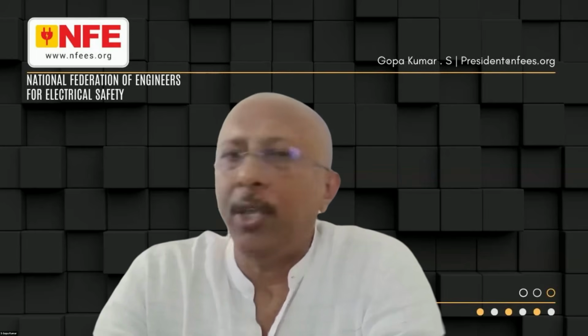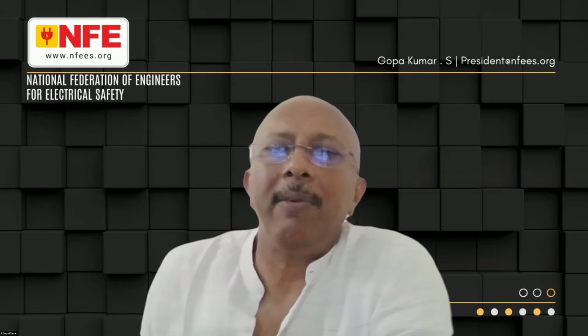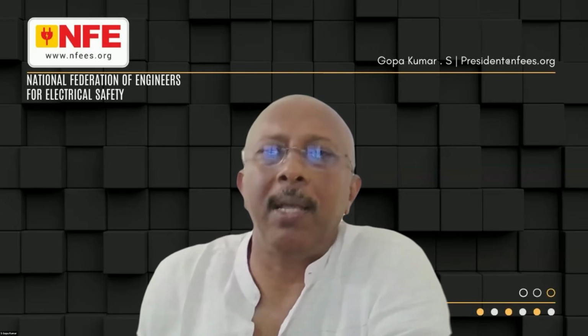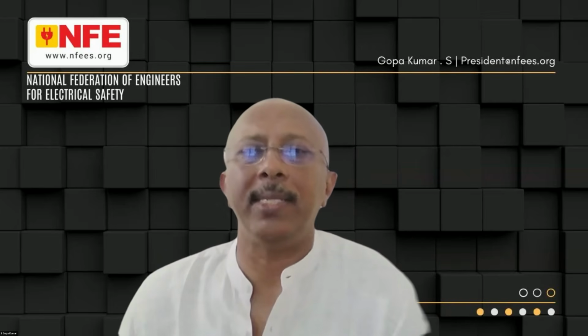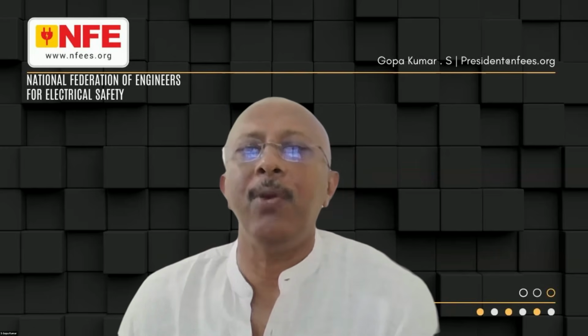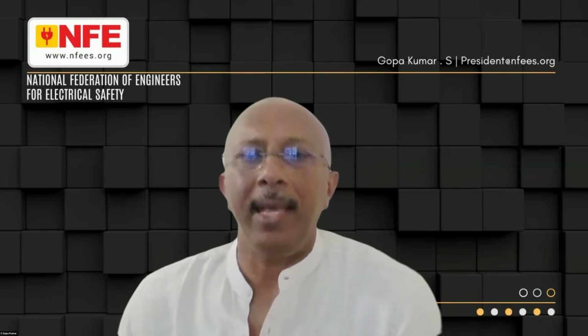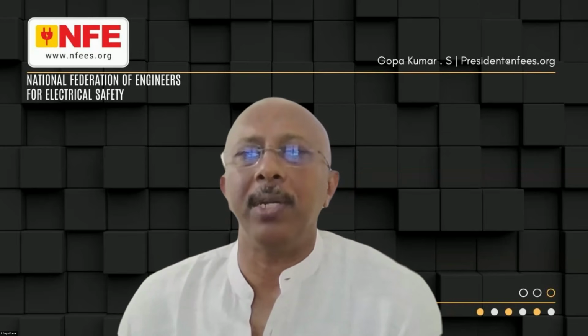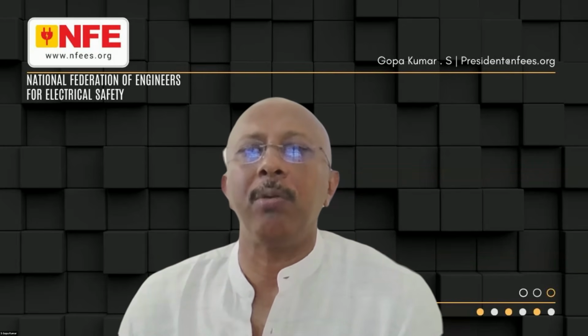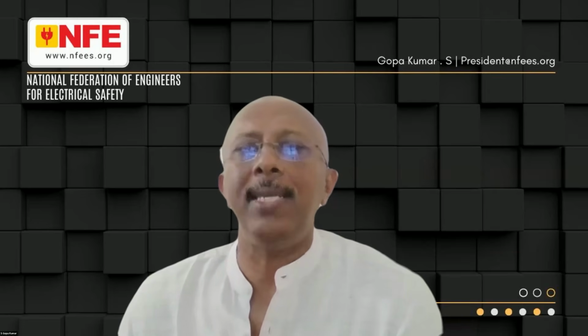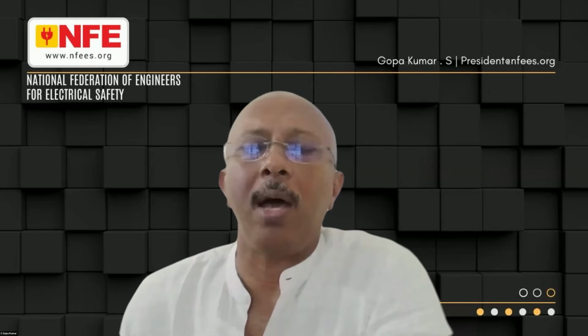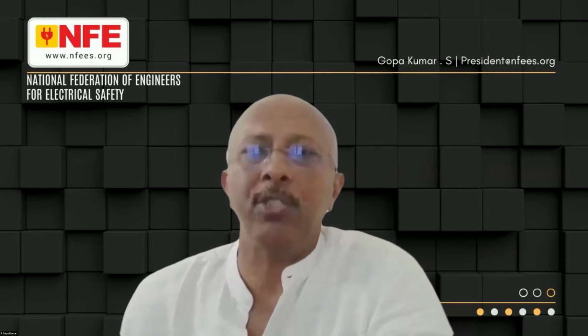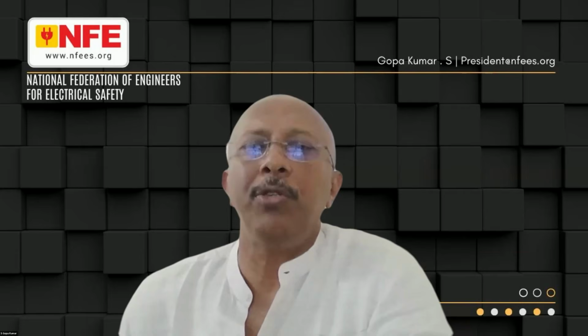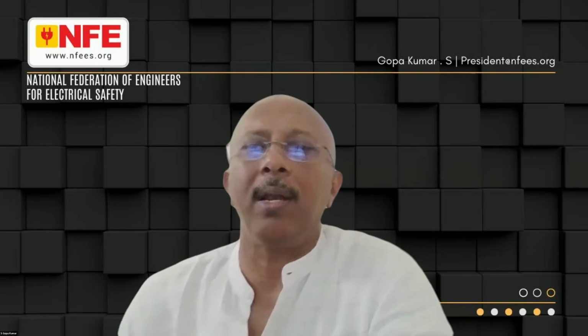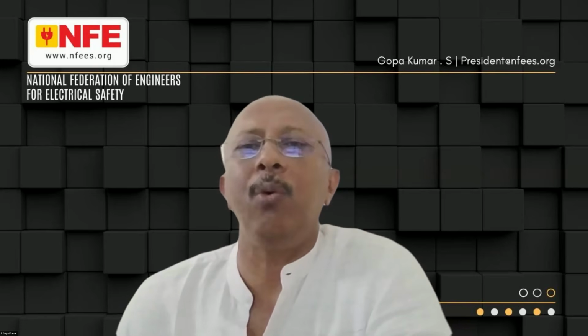Now, for a standalone equipment, even with 1 volt or maybe 5-6 volt, the equipment will work. But if two such equipment are communicating with each other, and if there is a potential difference in the neutral between these two equipment, the communication will malfunction. There won't be any communication because both AC equipment working in 230 or 400 volt are using the neutral for the reference of the PCB. One of the solutions is to keep the potential difference or potential build up in the neutral less than 1 volt. But please note, these are very old requirements.